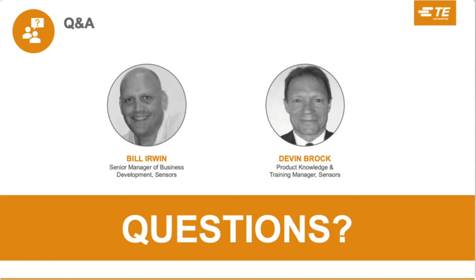Okay, Katie, this is Devin. I'll take that one. So, yeah, it's a great question, and yes, there are some differences. For example, first, the range and accuracies tend to be specific to a medical application. For example, a temperature sensor that's monitoring body temperature needs to be very accurate, but only over a very, very narrow range, around body temperature, so around 98 degrees Fahrenheit.